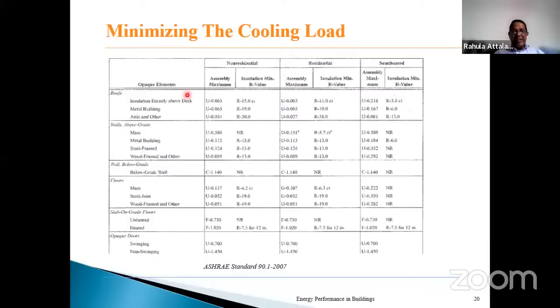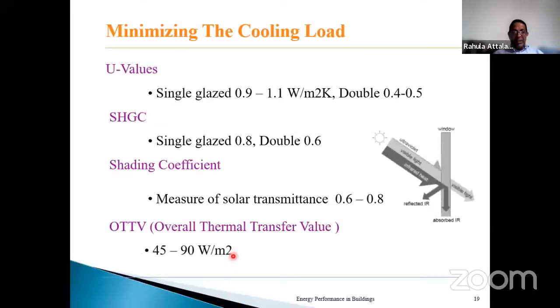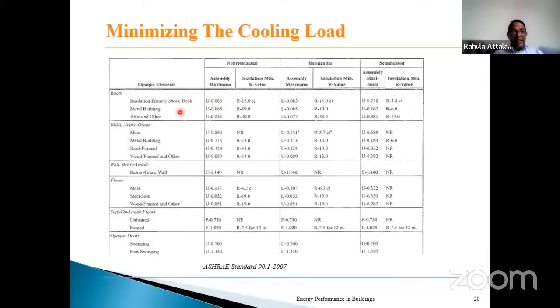And this is a table that you will see that I have captured from the ASHRAE 90.1. ASHRAE 90.1 is the ASHRAE standard for energy performance. So depending on the building type, non-residential, residential, or semi-heated building, and depending on the element of the building envelope, roof, walls, walls below grade, the underground, then floors, slabs, etc., it will indicate what is the value of the conductivity, that is this U value, and how this value should be maintained in each of these building envelope elements.